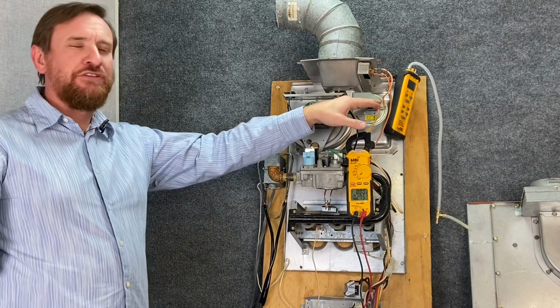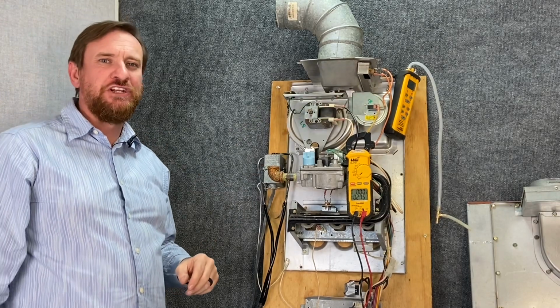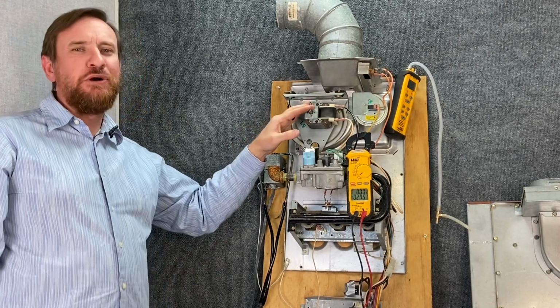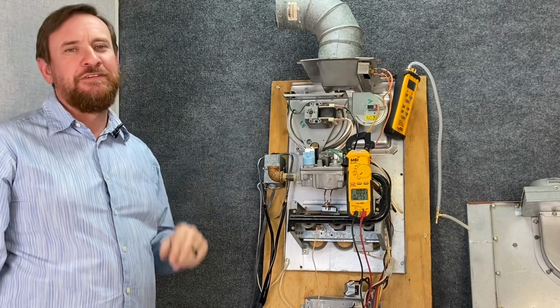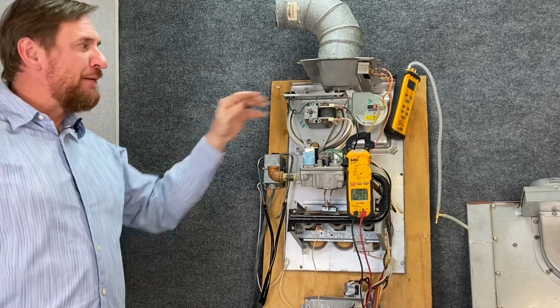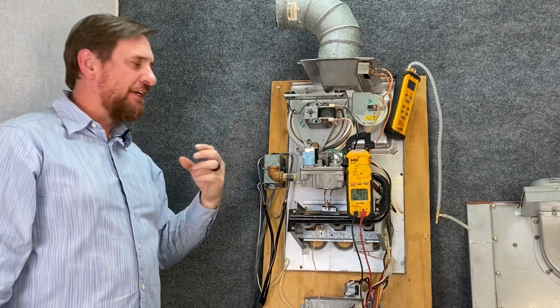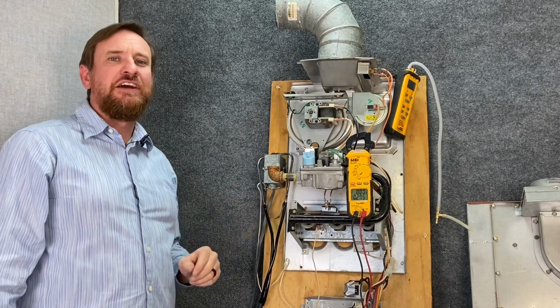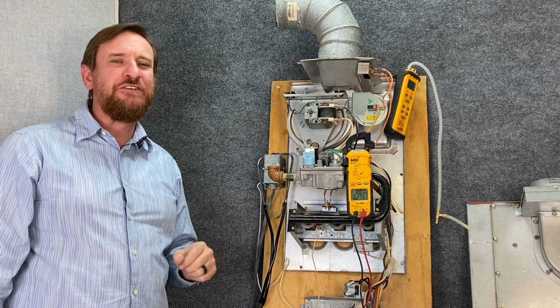Before we used vacuum pressure switch, they actually had a centrifugal switch. But the centrifugal switch just said the motor was working. It didn't say if we were pulling a proper vacuum to this pressure switch. Proper vacuum to the pressure switch means I'm also pulling the proper vacuum through our heat exchanger to make sure we have the proper air-fuel mixture.